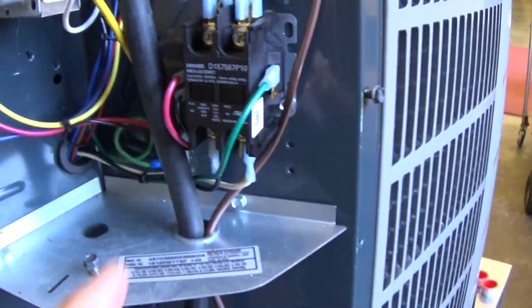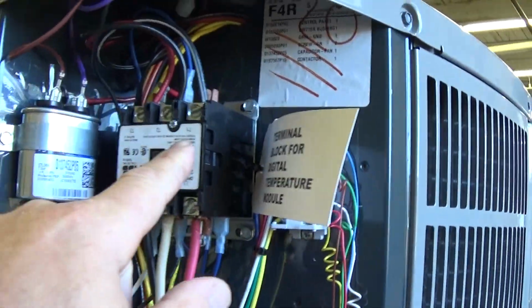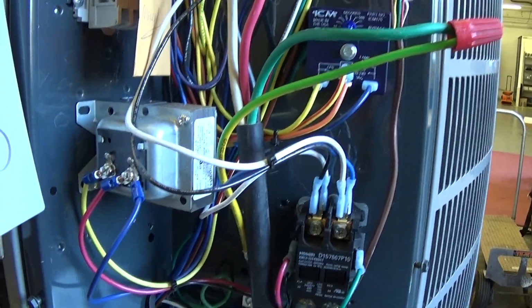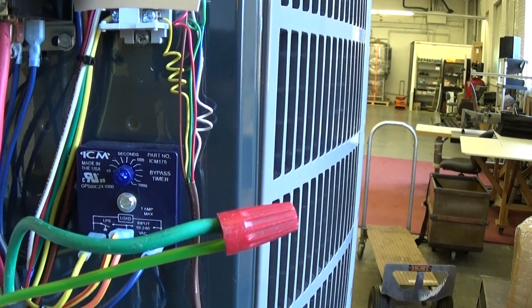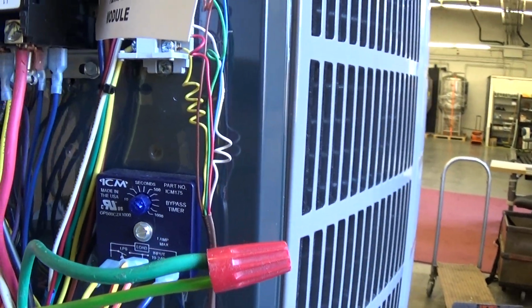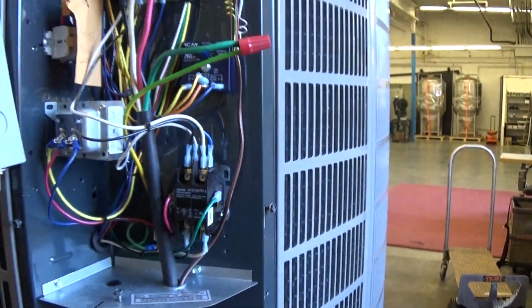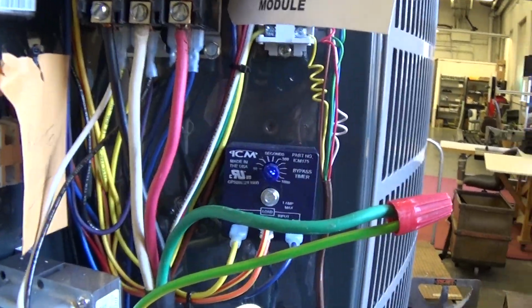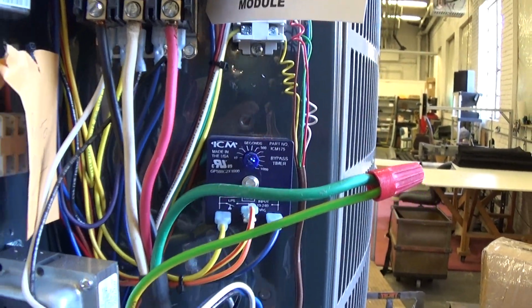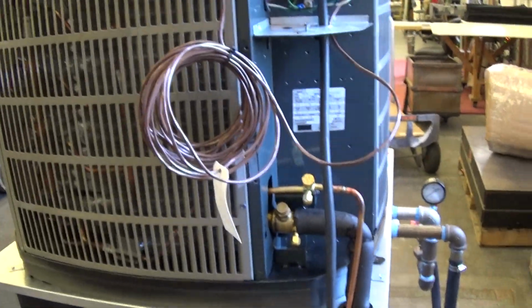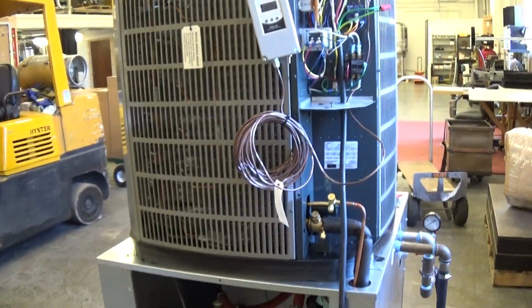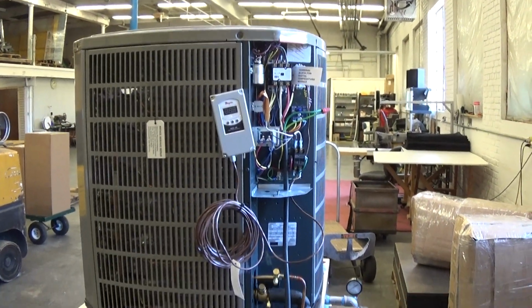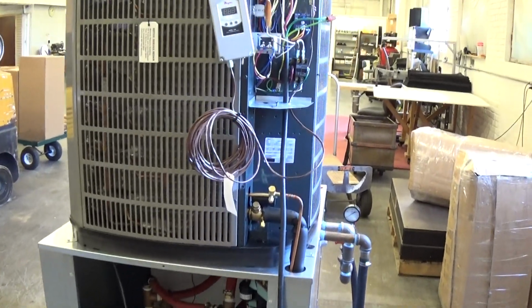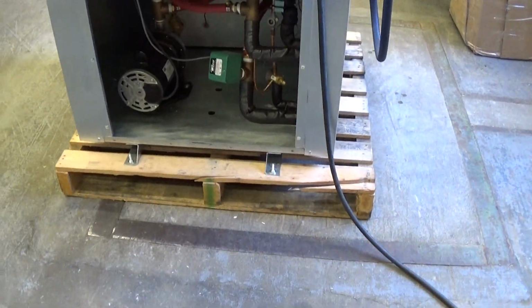This is our pump contactor on the chiller. This is our main power contactor. This is our controller transformer, and this is preset also at approximately 100 seconds, give or take. This is the low pressure refrigerant bypass that helps us on cold morning starts, so that the unit doesn't trip out on low pressure. On this unit here, the low pressure, high pressure, and fan switching pressure switches, and it does have fan switching for the low ambient control. They're all internal down below in the condenser, and they're also all auto reset, which is kind of a nice, simpler way of doing it.